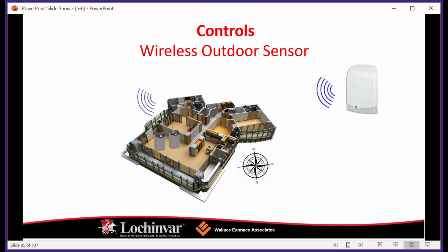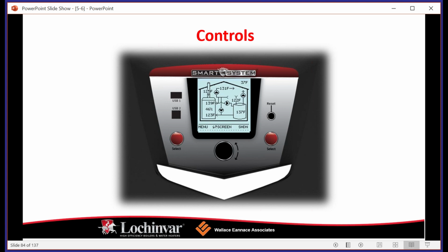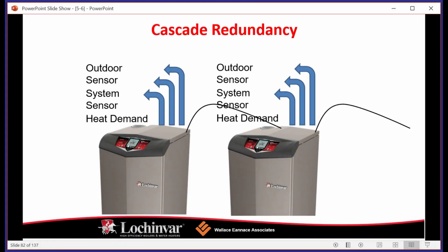And it's not always easy to do. You know, sometimes you've got a long run towards the north side of the building. Sometimes you've got structural stuff. You got poured bluestone. You got a whole bunch of stuff you need to punch through. You can get, as an aftermarket piece of equipment, a wireless outdoor air temperature sensor that will speak to the boilers, so you don't need to snake that wire through the structure if you're unable to get to that north side of the building. So kind of skipped ahead a little bit. Let's go back here. So again, the smart system is kind of showing us what you can expect to see from it.